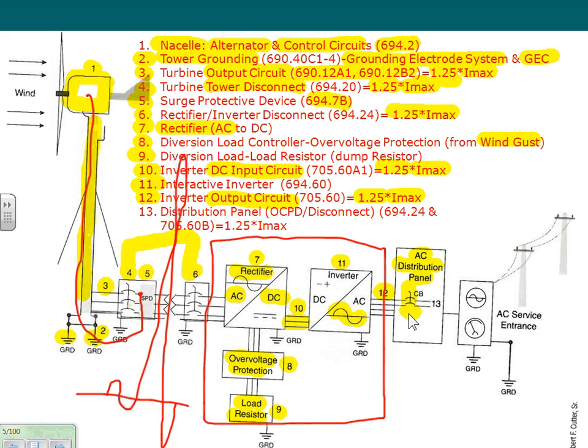So that's my inverter. And the last thing, also being designers and engineers, we need to know what's the overcurrent protection device. You have to have an overcurrent protection device right in here. We size it also based on 125 percent of I max, so 100 times 1.25, you have a 125 amp circuit breaker or fuse, and you put it inside this panel.